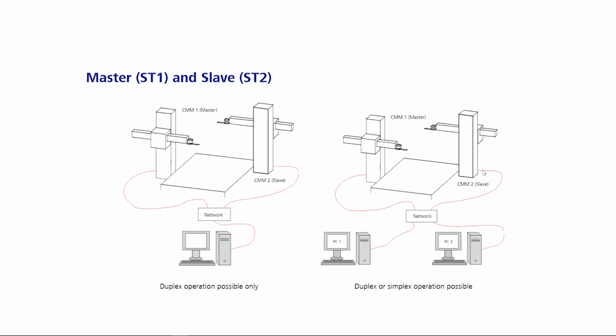Since the configuration with two computers is more common, I would like to discuss this in the following and refer to the right picture. Here, control is only done by the master PC and CALIGO may only run on the master PC. The slave PC only runs along, just like the slave column. Therefore, all columns must be deselected on the slave PC. After that, CALIGO must of course be closed there, otherwise no operation is possible. Let's summarize once again. CALIGO must only run on the master machine and the master computer. Both columns are controlled from the master computer.